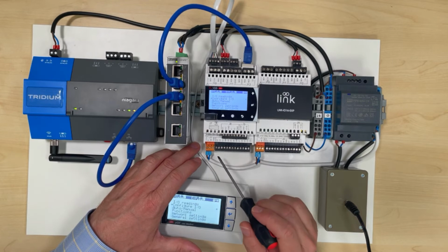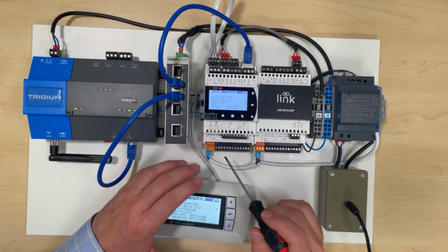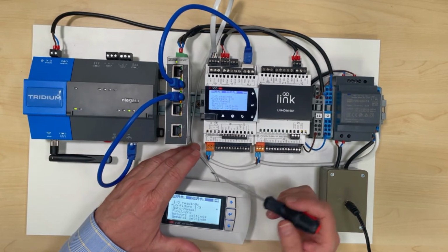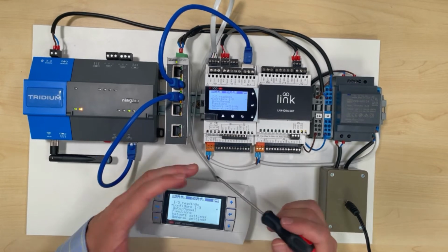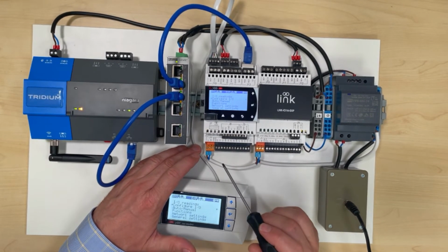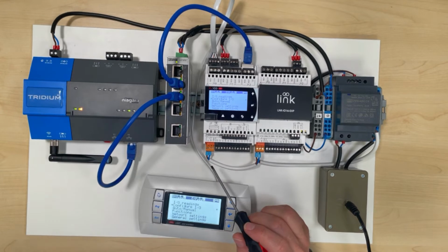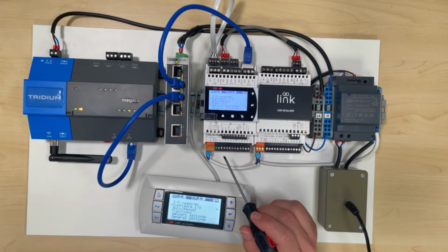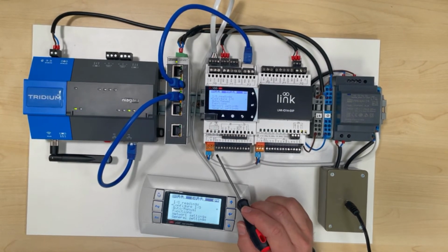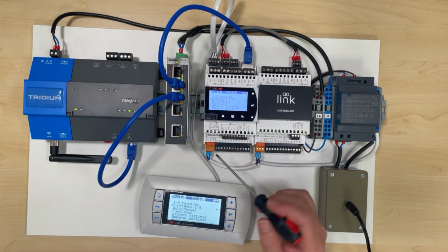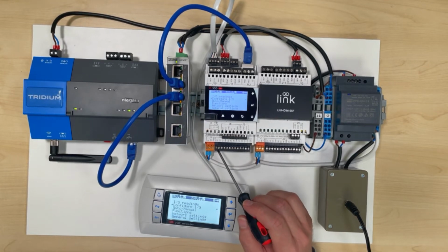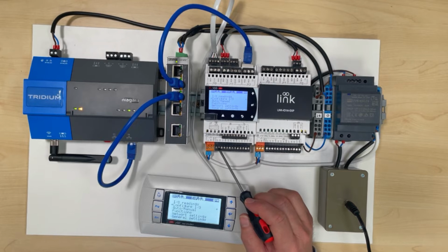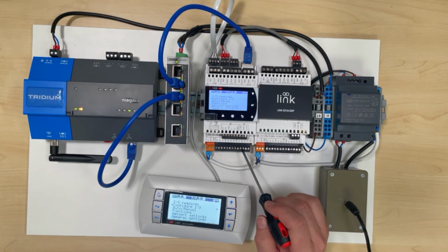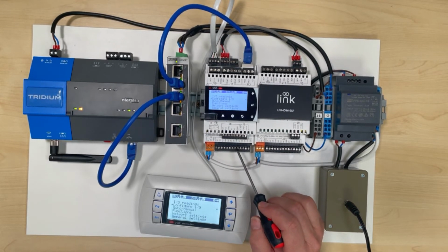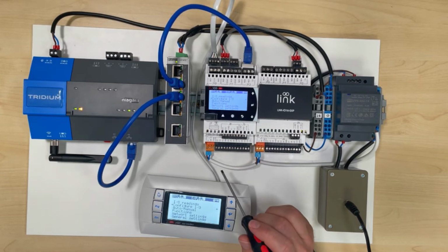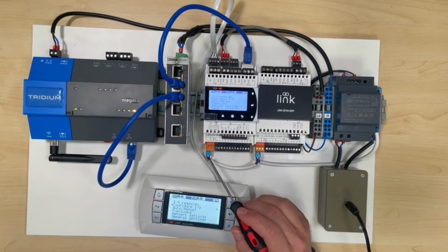As far as analog inputs are concerned, we could use passive inputs such as thermistors or resistive inputs like potentiometers, things like that. There is a limitation if you use PT100 3-wire detectors. There's a limit of 5, and the reason for that is if you use one channel as a PT100 3-wire, you must set the next one to not use. That's just a limitation, so you can have 5 maximum there. You must take that into account if that's what you're doing. So active inputs, you can have 0 to 10 volt, as many as you like.